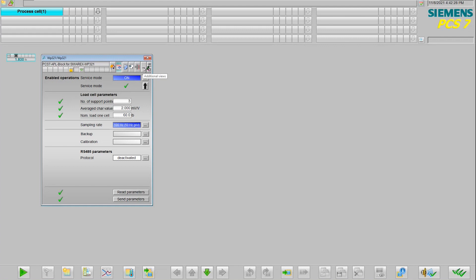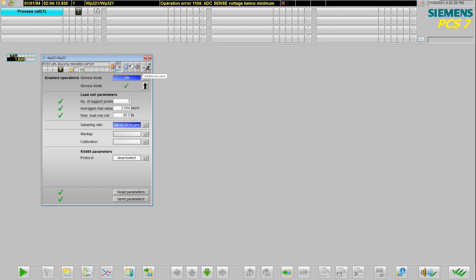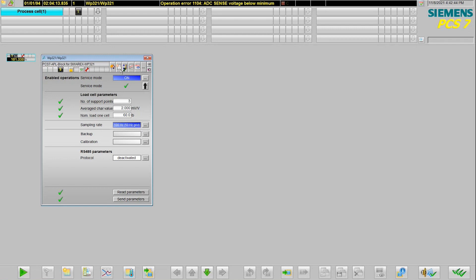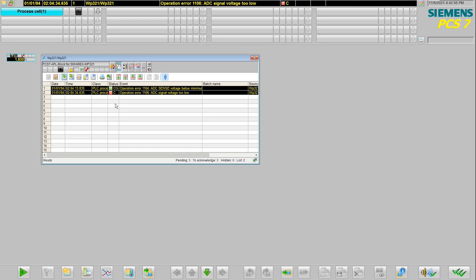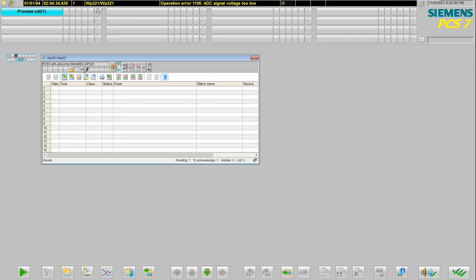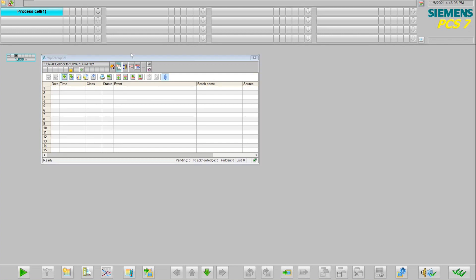So here, if I trigger an alarm by disconnecting my load cell, I can see that I immediately get an alarm in my top banner, in my block icon, as well as in my faceplate. We're alerted at all levels of the diagnostic error. Once I rectify it by fixing my connection, we can see that that error is going to clear. I can acknowledge that, and now my runtime is clear of errors and I'm back to normal operation.